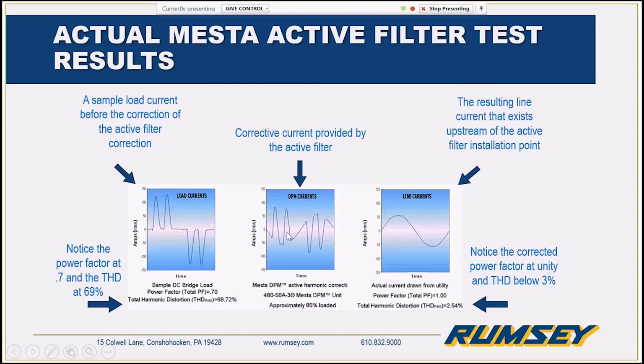Here we see the injecting current that the active filter is putting into the line, so it's the net canceling current, and then the resulting sine wave that's upstream of us. So you can see it being corrected below 3% and correcting that power factor to unity. We were originally designed with that hospital specification in mind, the old one of trying to be below 3%, but we can definitely meet the 5% specification that's out there now.